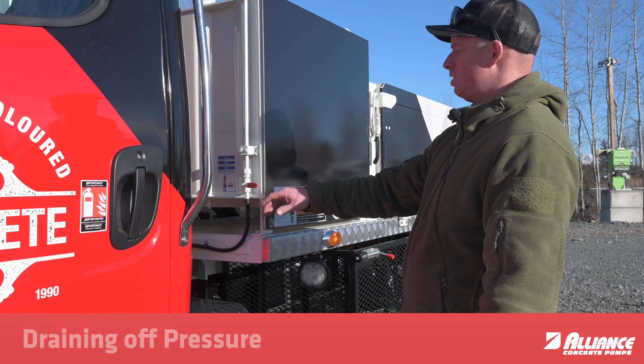You want this gauge to read between 0.5 and 1 bar. If you're any lower than 0.5 of a bar, you want to check your air regulator, make sure it's working correctly, and adjust it to suit. So at the end of each day of pumping, we recommend draining off the pressurized hydraulic tank. This will allow the system to be de-energized with the pressure in case there's an oil leak. And then what we recommend is when you go to start your day, to close this valve before you put it into PTO, and then the tank can re-energize, and then you will have no cavitation on startup.